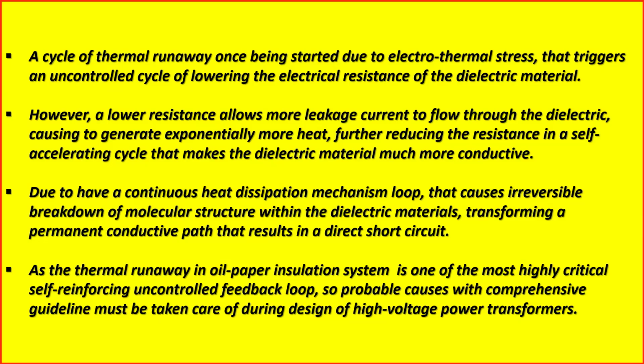Due to this continuous heat dissipation loop, it causes irreversible breakdown of the molecular structure within the dielectric materials, forming a permanent conductive path that results in a direct short circuit.